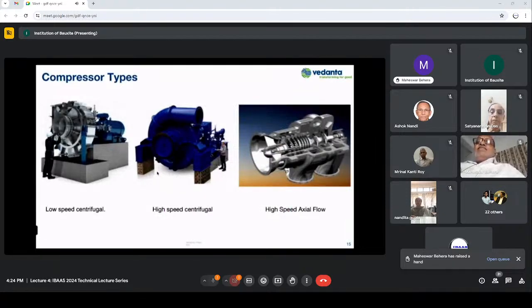So these are the types of MVRs. The first one is the low speed centrifugal compressors. These typically operate around 3000 RPM or lower, and are directly driven by electrical variable speed motors. They are robust and make up most of the MVR market, and the technology is very proven. Then come the high speed centrifugal compressors, with high compressor efficiency and high impeller tip speed. They run at around 7000 RPM or more, are gear driven, and take a lot of space at the plant. The third one is the high speed axial flow compressors, which have very high volumetric capacity and are also very compact. So for retrofitting scenarios, they are very useful.